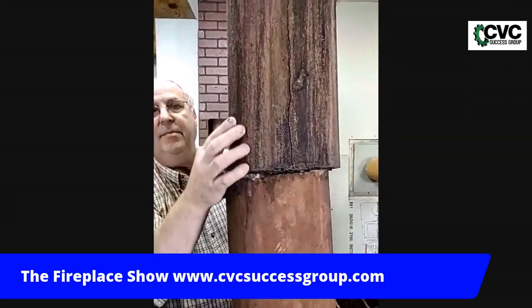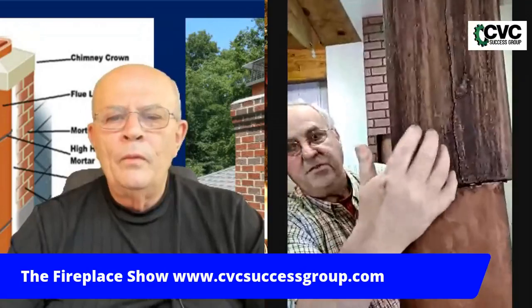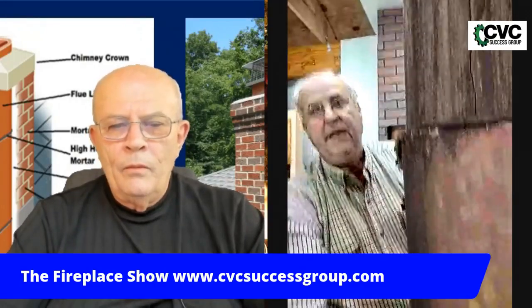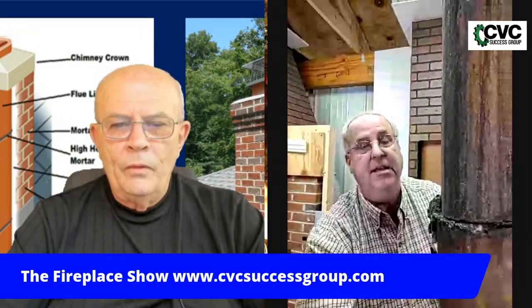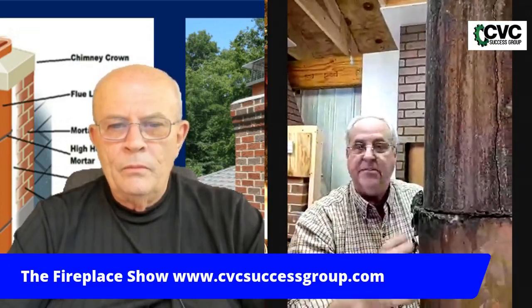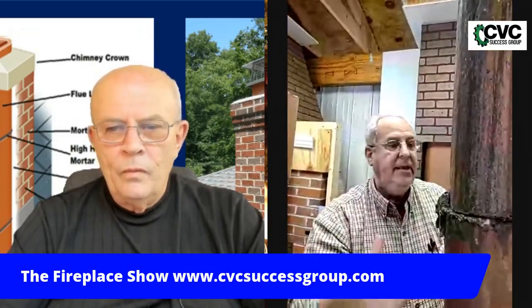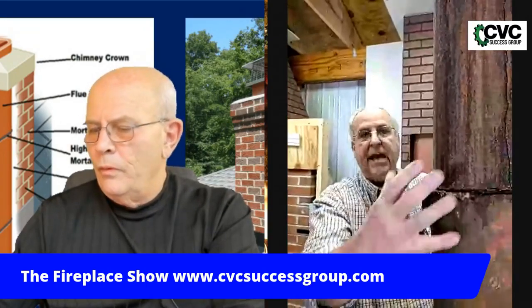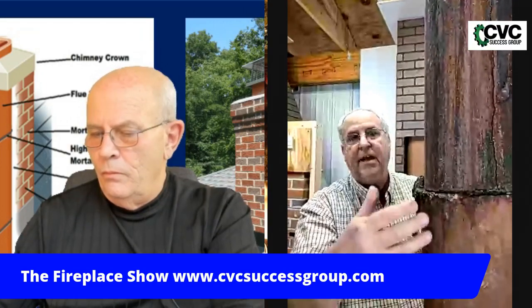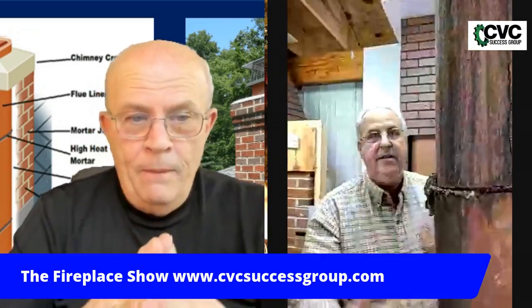Here is how these liners were positioned in the chimney when they were taken out together. The condensate has sweated through and is now on the outside of the chimney — that's what we don't want. We want liners to contain the products of combustion, not allow gases and condensates to escape. There are tens of millions of chimneys in the United States looking very much like this one — poor performers that won't work as well as they should.